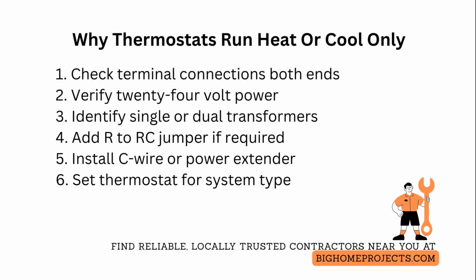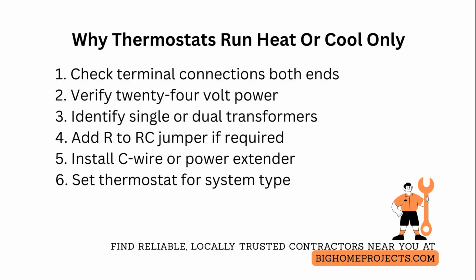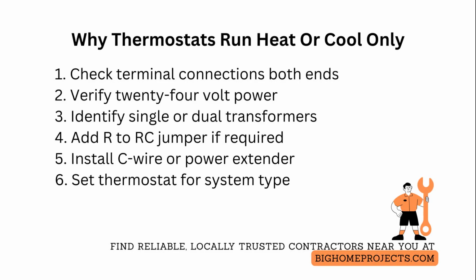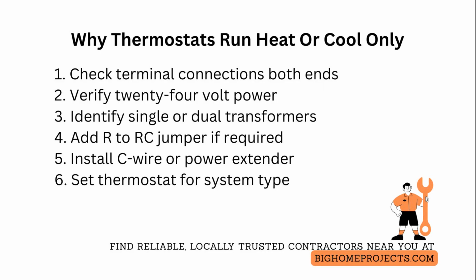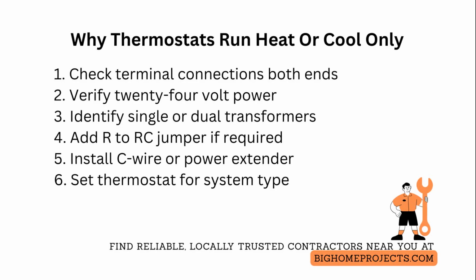Confirm the correct use of a jumper between the red and the red cooling terminal when the system design requires it. Some older systems expect an R to RC jumper or similar, so the thermostat has power for cooling control. If the thermostat is battery-powered but still lacks a common, consider adding a C-wire or a power extender kit to stabilize control signals. Inspect the heat pump configuration switch or settings in smart or universal thermostats.